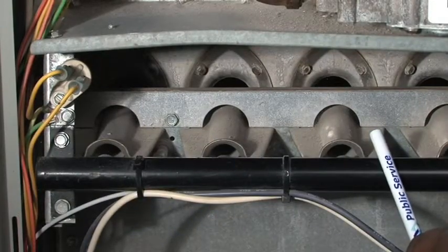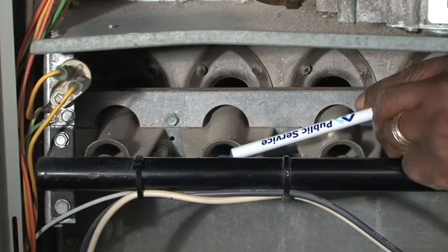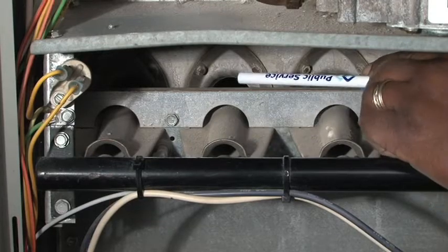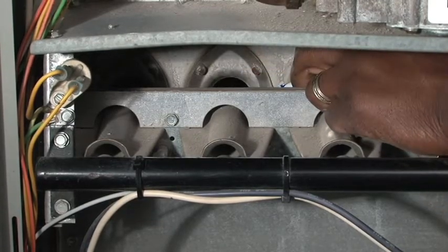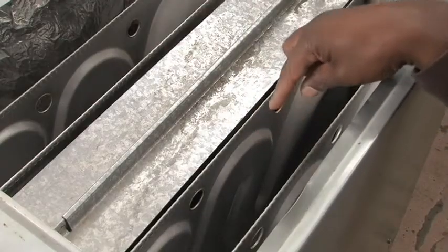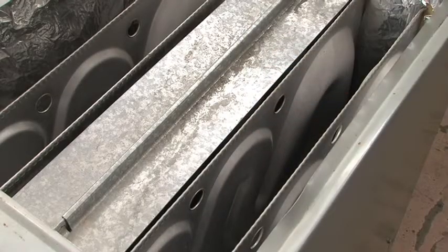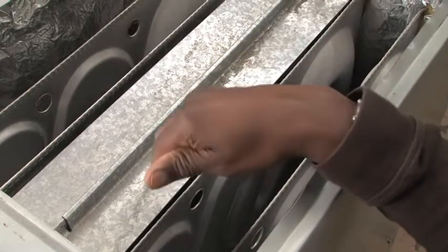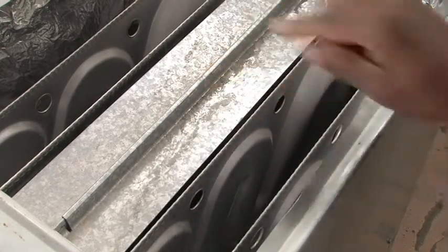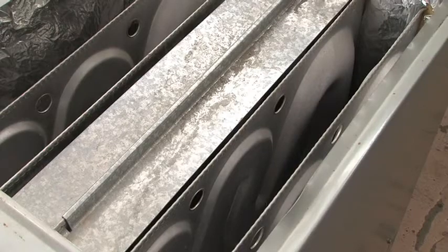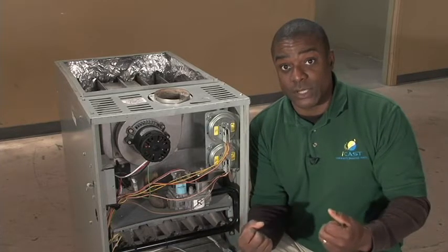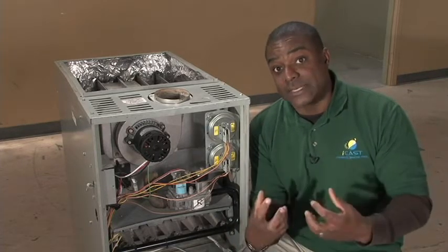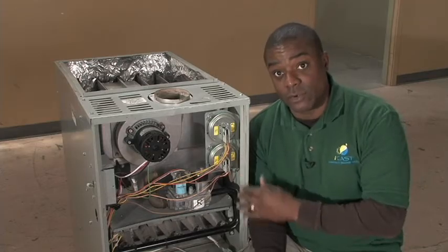These are the gas valves. Gas comes out here, goes through the orifice, then we have a flame on the other side that goes into the heat exchangers. If we look at the heat exchangers in the 80% efficient furnace, we notice that there's a serpentine pattern. That forces the combustion gases to spend more time in the heat exchanger, allowing us to extract more heat out of those combustion gases. And that adds to the efficiency of this furnace.